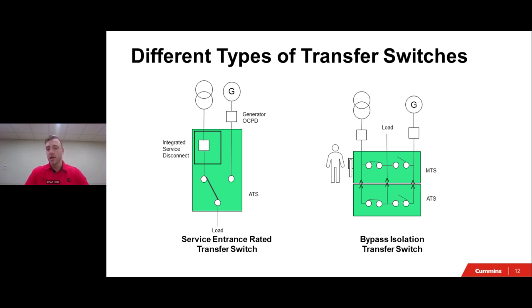So as you can see on the diagram, there's a little split in the middle. So you have that automatic transfer switch on the bottom and your manual transfer switch on the top. Normally they are connected together, but say if there is testing that needs to be done or you're doing maintenance on the transfer switch, you can split those and the manual transfer switch will still be connected to the emergency and normal power source. If you need to transfer power, you can then manually transfer the power while the manual transfer switch is still connected.